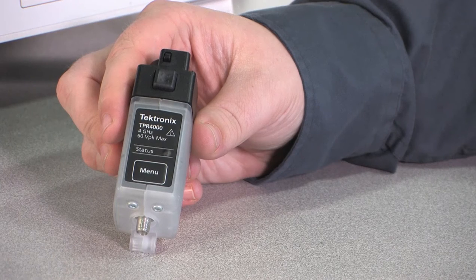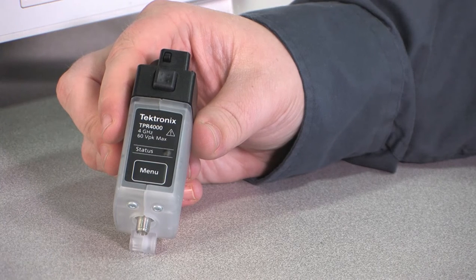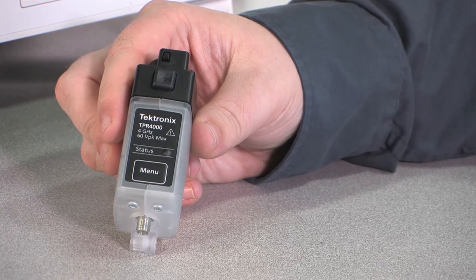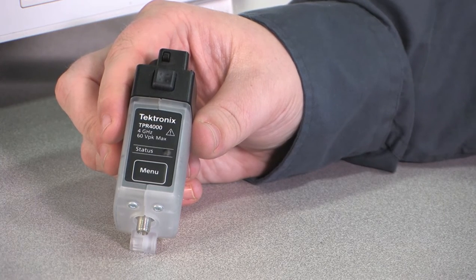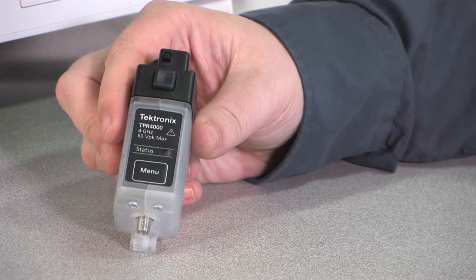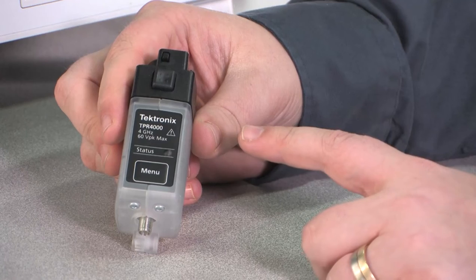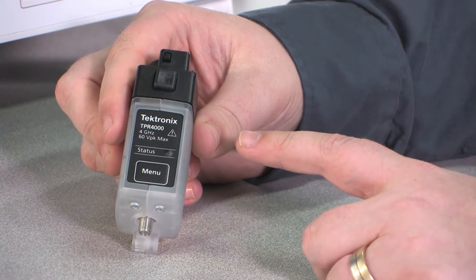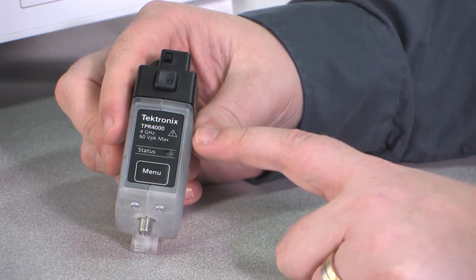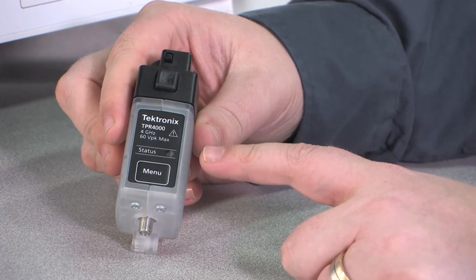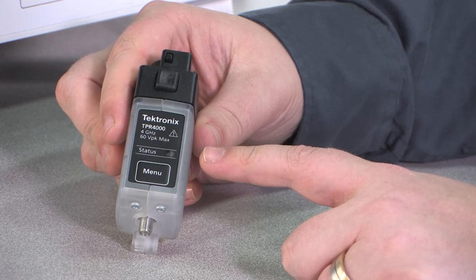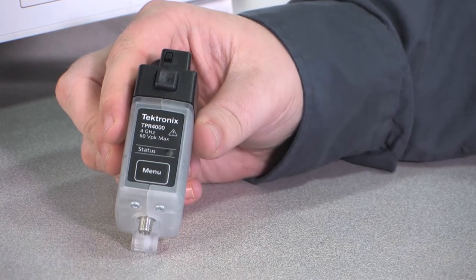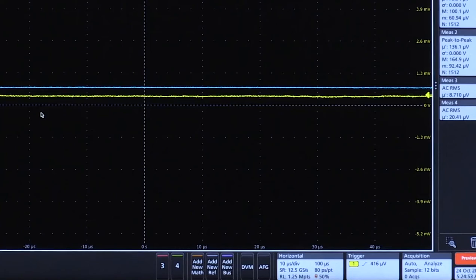The TPR-4000 is a 4 gigahertz power rail probe, which will also come in a 1 gigahertz model that goes up to 60 volts in offset, both plus and minus. There's a plus or minus 1 volt dynamic range, and we'll see in a moment the noise spec for the TPR-4000.